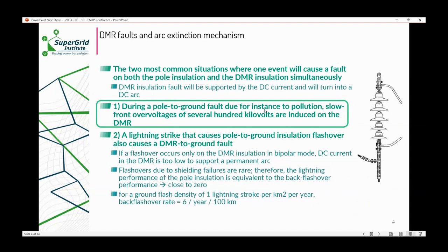Why is it a problem? You can see a figure on the top right. Usually, pole conductors are quite long, and pole insulators are quite long compared to DMR. DMR is usually insulated only to the voltage it sees as a voltage drop across the DMR. We see this as a weak link of the system, and we are trying to look at how does this short insulation behave during different faults and overvoltages. This paper studies the behavior and extinction of arc on insulators of a DMR conductor and practical solutions to limit the risk of permanent faults.